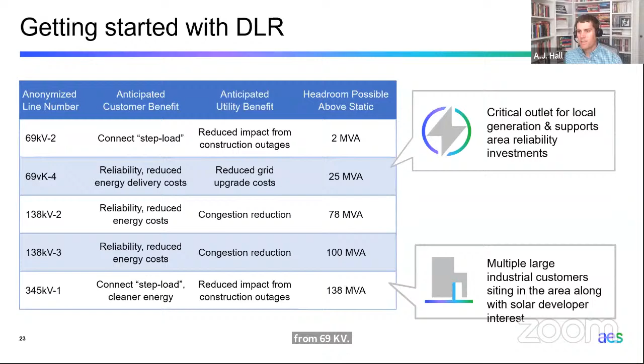So how is the installation? I like to say there's no transmission physical infrastructure you can install faster than DLR. It sometimes takes me longer to log into my computer in the morning than it takes to install one of these sensors. Typical sensor installation can be done, as you see on the top right, from a 15-foot ladder. These sensors are mounted to existing poles or lattice towers well below the safety clearances of conductors, working at live voltage, so no outages are required to install them.